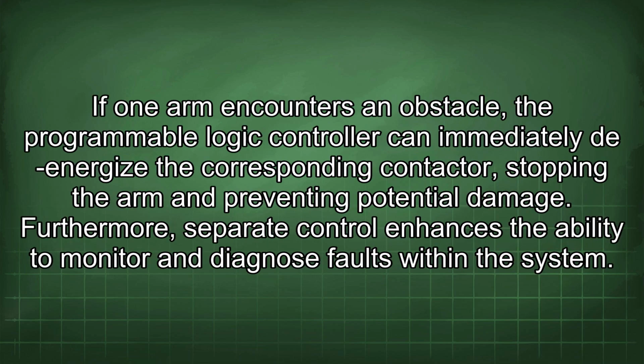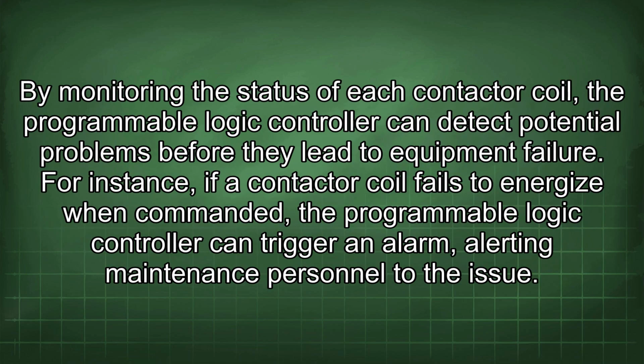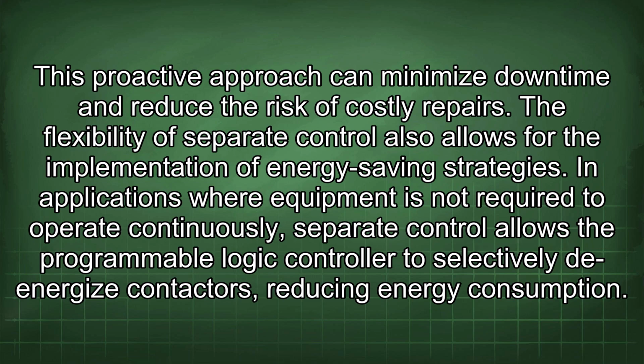If one arm encounters an obstacle, the programmable logic controller can immediately de-energize the corresponding contactor, stopping the arm and preventing potential damage. Furthermore, separate control enhances the ability to monitor and diagnose faults within the system. By monitoring the status of each contactor coil, the programmable logic controller can detect potential problems before they lead to equipment failure. For instance, if a contactor coil fails to energize when commanded, the programmable logic controller can trigger an alarm, alerting maintenance personnel to the issue. This proactive approach can minimize downtime and reduce the risk of costly repairs.